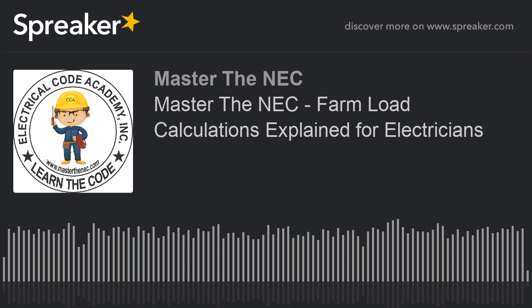All right, so the next thing we're going to move to is other than dwelling unit. So this is 220.103. It says other than dwelling unit. Now this is all of those loads that have nothing to do with the dwelling unit, okay? It says where the feeder or service supplies a farm building or other loads having 2 or more separate branch circuits. So again, I could feed a panel, and out of that has 2 separate branch circuits feeding 2 or more different loads. And you would use this method to do that.